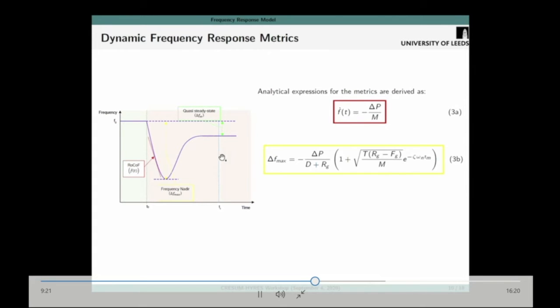The second metric was the change in frequency, the nadir. This can also be a frequency zenith depending on the power exchange with the main grid. And the change in frequency nadir is dependent on the step change in power, the normalized damping, the normalized droop in the network RG, the normalized system inertia, and the turbine time constants of the different generators, T here. As we can see, the change in frequency nadir is a highly nonlinear metric. The final metric is the change in quasi-steady state frequency, and this is dependent on the step change in power, the normalized droop, and the normalized damping constant.